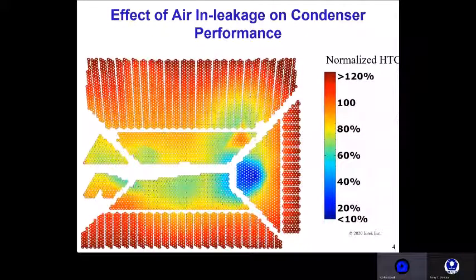This example from another power generating facility shows a condenser with the air remover section on the left of the tube bundle over here. And unlike the previous unit, there was no baseline tube fouling found in this condenser. The major difference being this deep red represent hot temperatures at the peripheral of the tube bundle and a cleanliness factor of 100 to 120%.